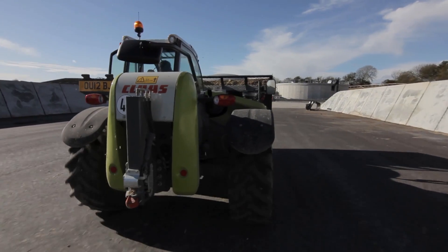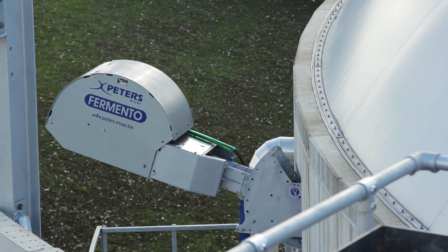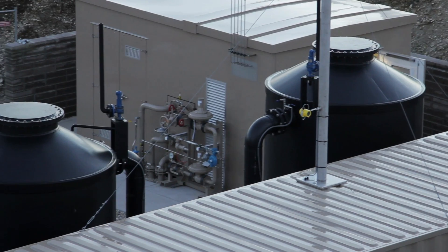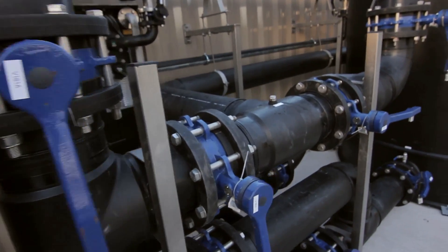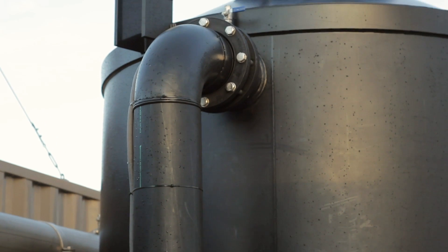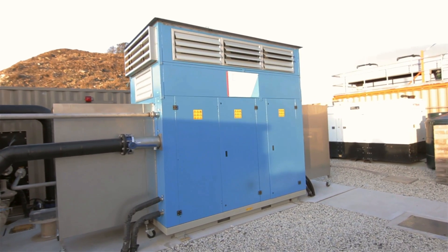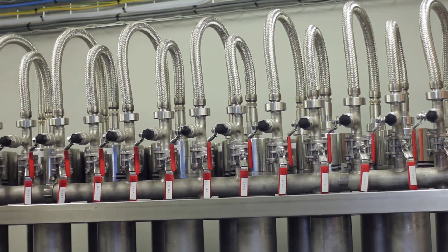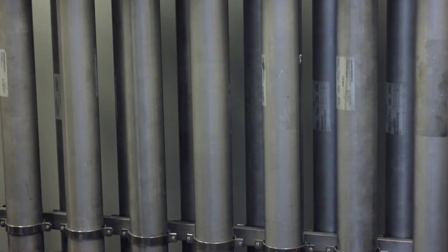When we first looked at gas cleaning, we were concerned about the complex technology — how to go from a bit of kit that cleans the gas to a bit of kit that puts it into the gas main. So we joined in with Southern Gas Network to help us create an easy solution of going gas to grid. This is the gas cleaning machinery made by DMT. The basic process is that the biogas comes in and is sucked through these large black containers, filtering it and concentrating the methane so that it can be injected into the national grid. The biogas then goes to a large blue compressor, which compresses it and forces it through membranes inside the cabinet. These membranes separate the carbon dioxide and the methane.